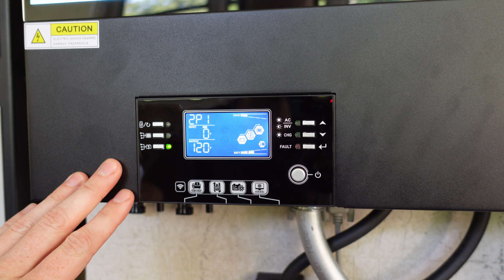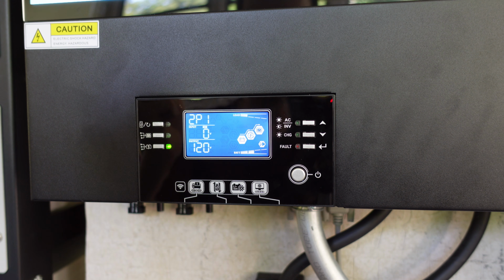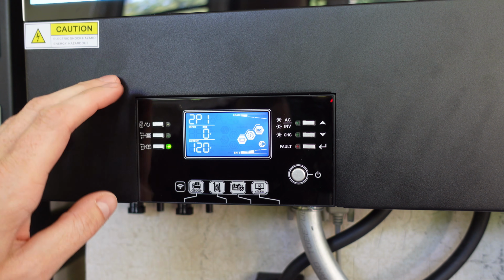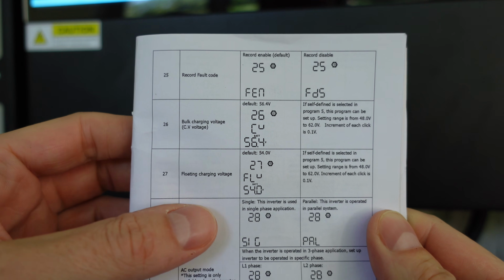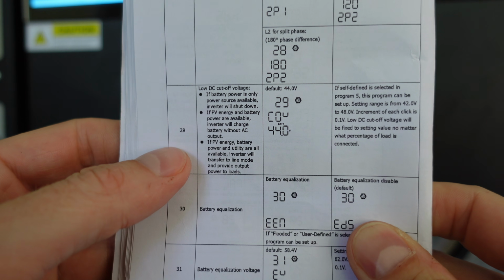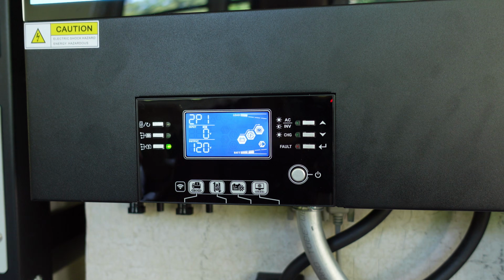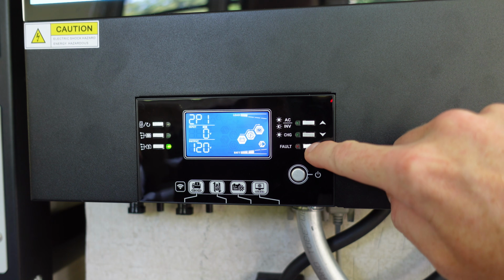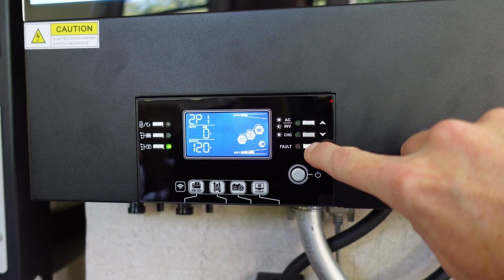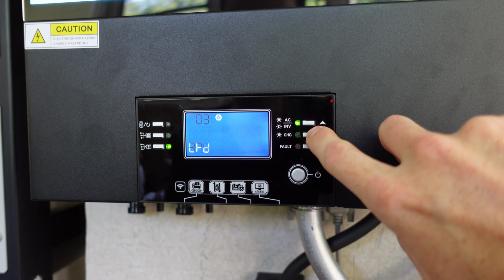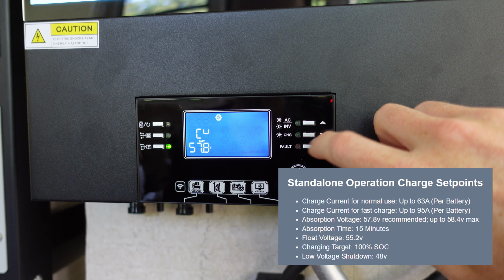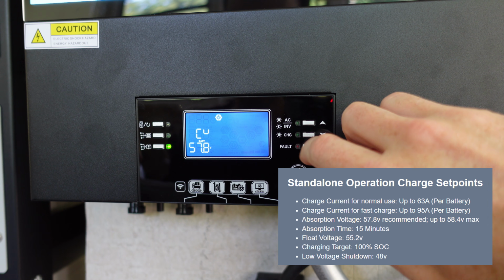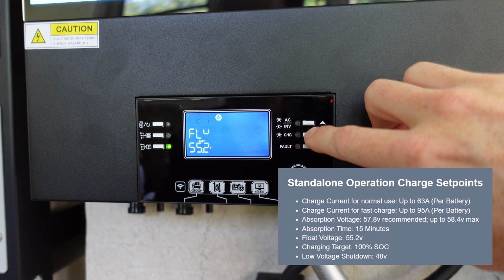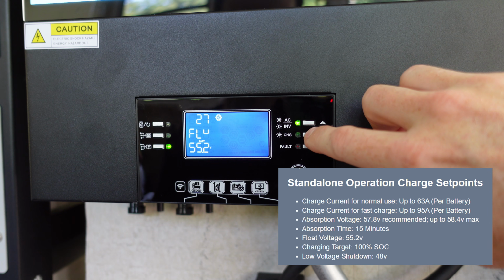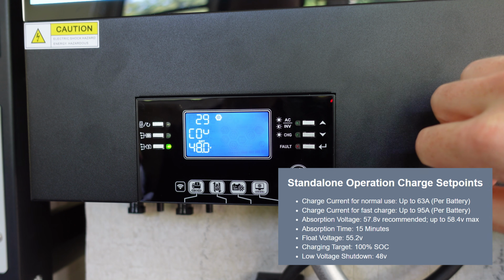So one last thing before we test out our inverters is we need to set the voltage parameters. Those will go into settings 26, the bulk charge voltage, 27, the float charge voltage, and then 29, the low voltage cutoff. So we don't have communication set up with this yet. We'll cover that in a separate video, I think. I'm actually having some firmware issues with this inverter. So I've used the values recommended by SOK, which is a bulk voltage of 57.8, a float voltage of 55.2, and a low voltage cutoff of 48 volts.